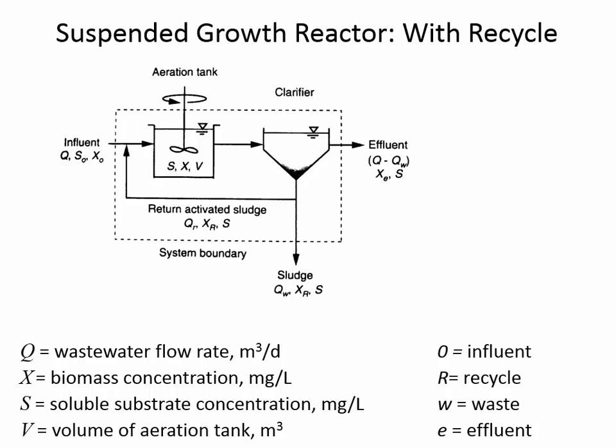You'll notice that the stream branches. Some of the sludge is returned to be recirculated into the aeration basin, and some of the sludge is wasted. If we didn't waste the sludge, then solids would accumulate inside of this loop, and both of the tanks would fill up with solids. And so we have to have some wasting of solids, and that's why there's this underflow that's going to a separate treatment system.